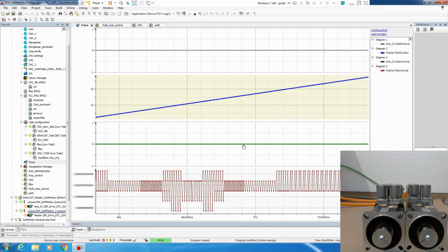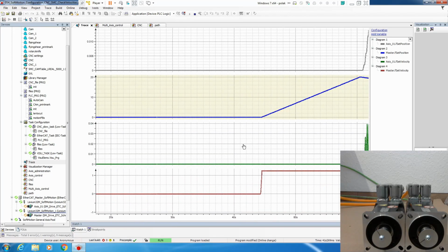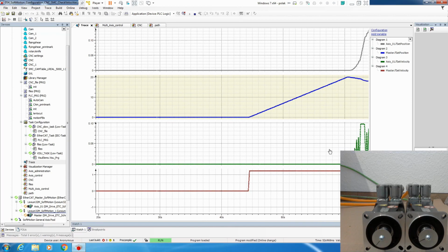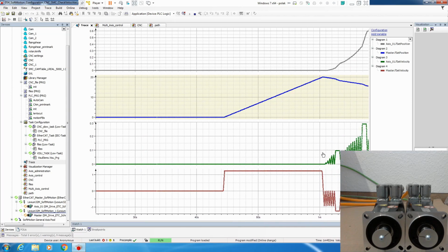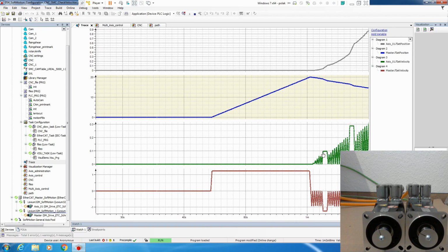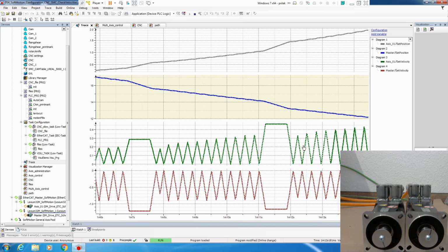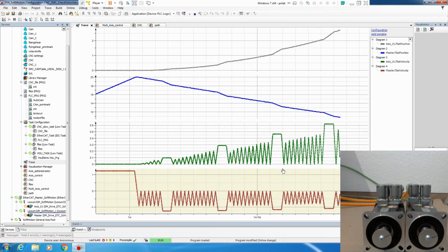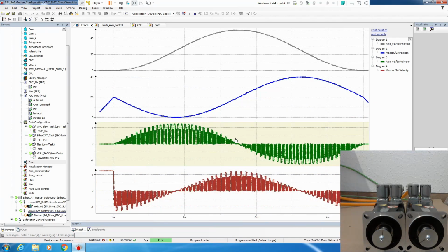Let's go to the trace and check it out. So here, first we see the positioning, and now it starts, and immediately you see the problem, which is also visible on the shaft of both motors. Each motor is trying to do the segment, so it accelerates, goes to a certain speed, and then it decelerates. Now execution of the complete path is done.